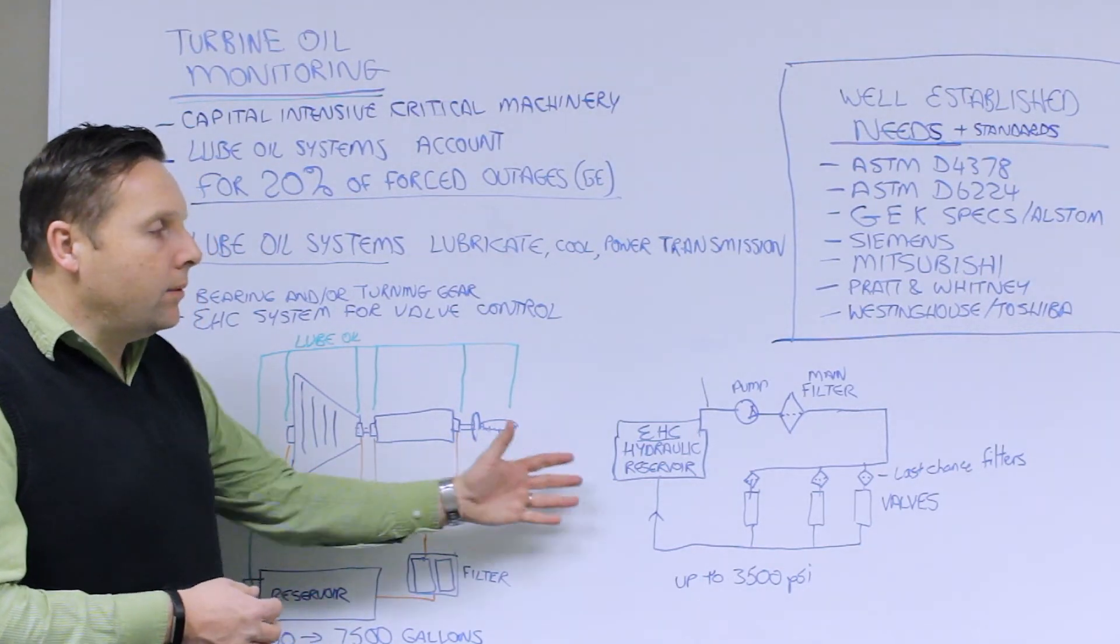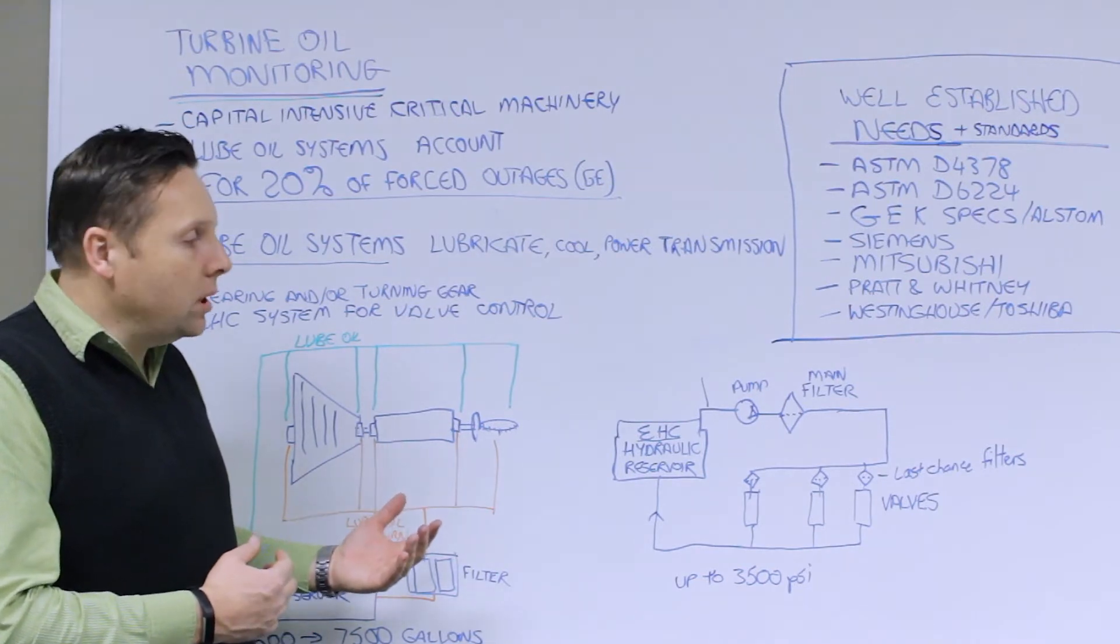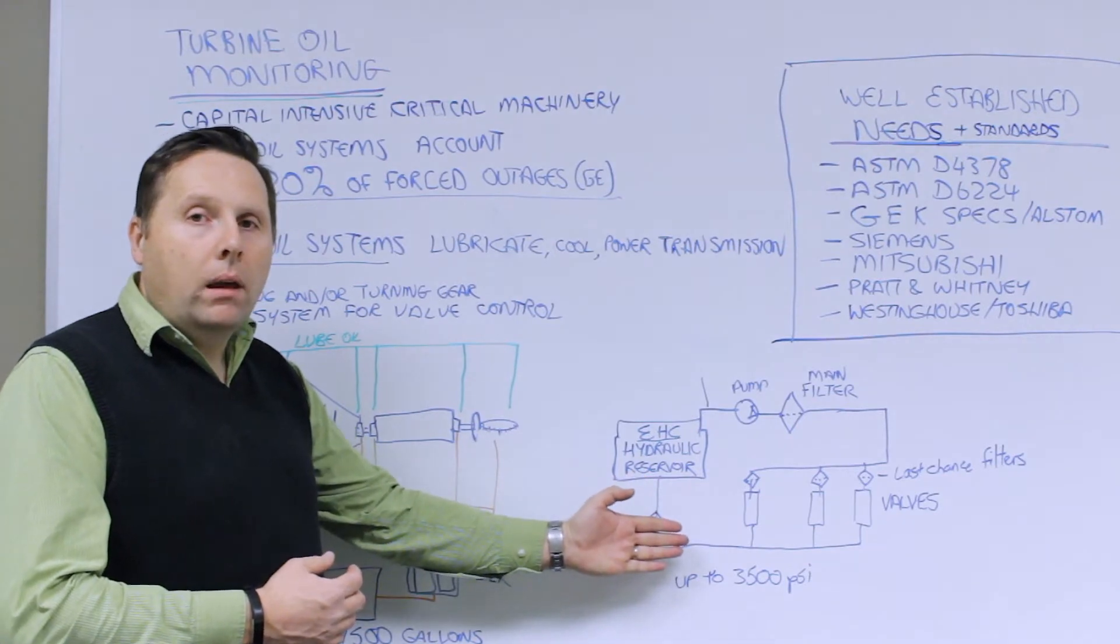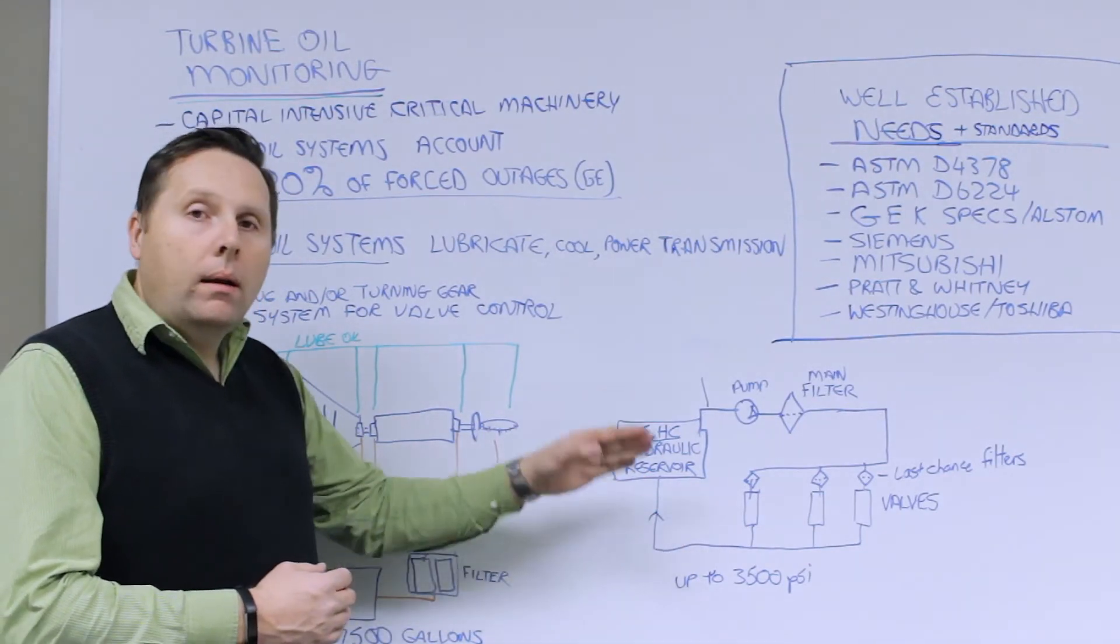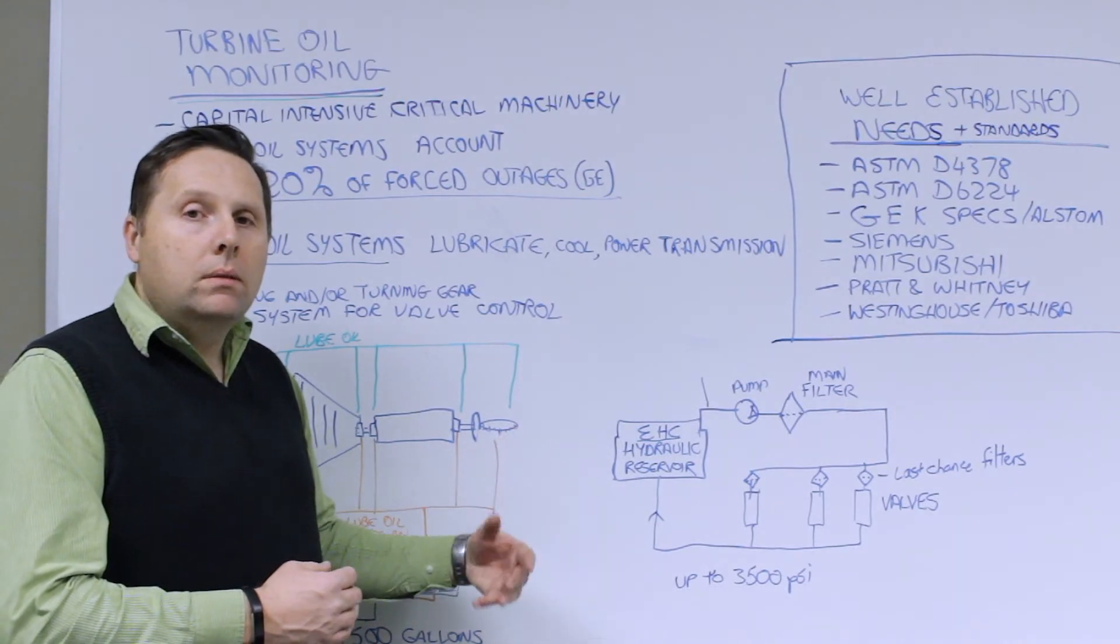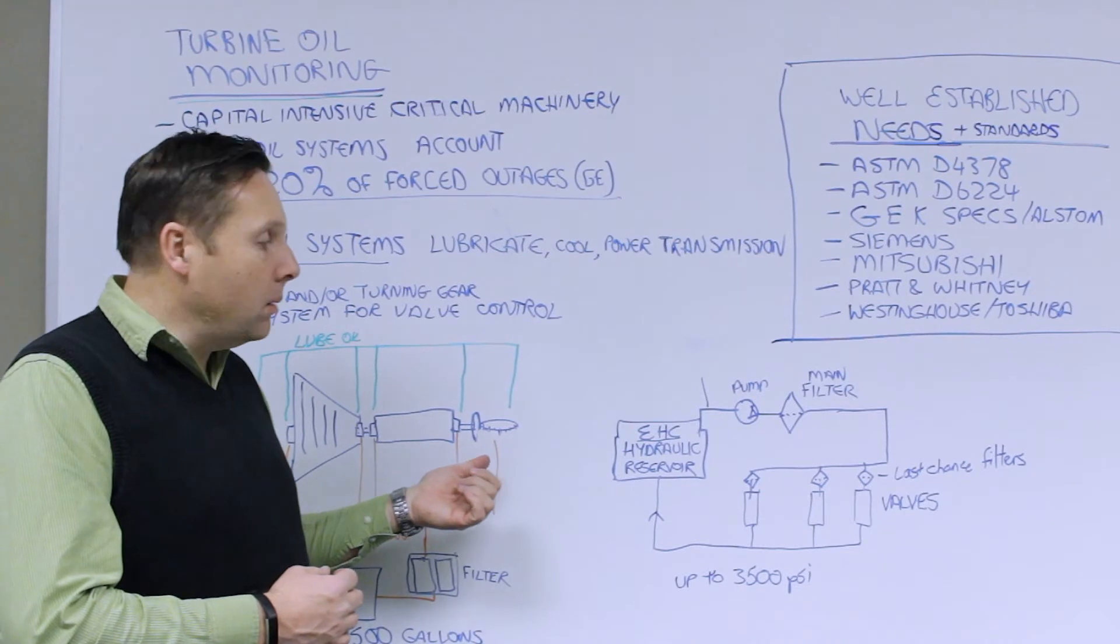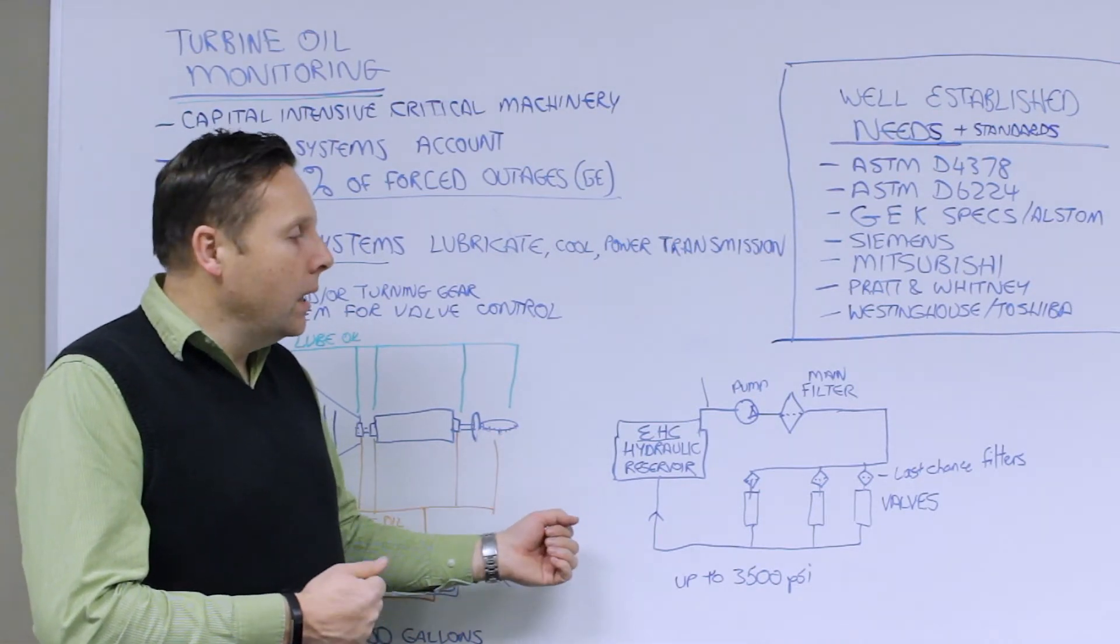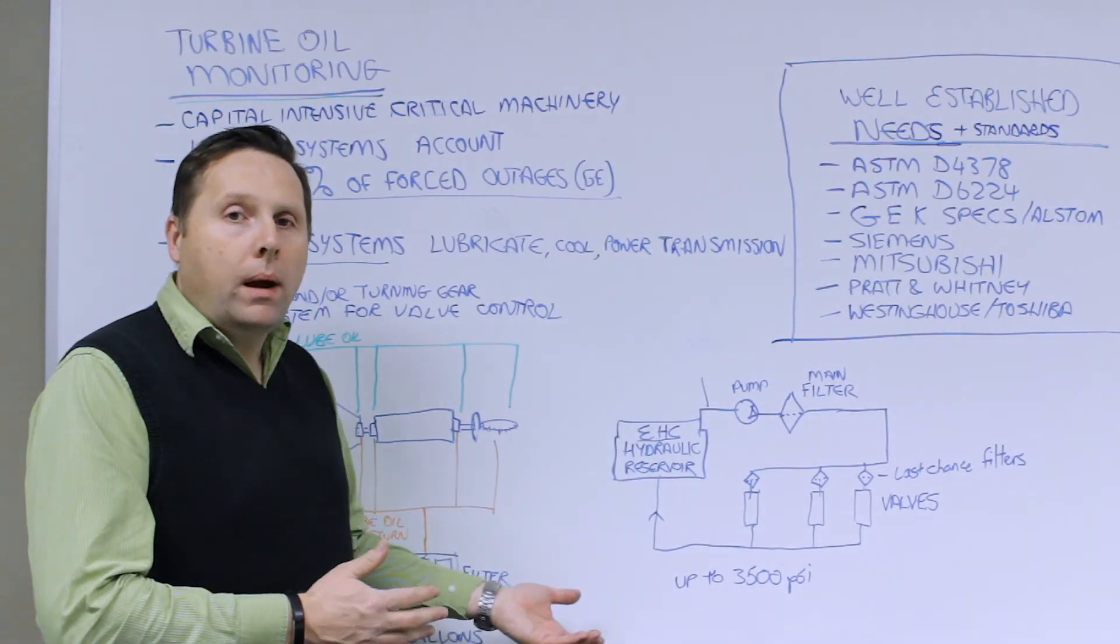Separately you can have an EHC or electro hydraulic control system. Traditionally on older steam turbines, these were a separate system that were designed to control the valve positioning for the steam. Generally consists of a fluid that was able to withstand the high temperatures that are encountered during the steam. So you'd often have a phosphate ester or Fyrquel style system on the older systems. You'll still see this on a lot of power plants today.